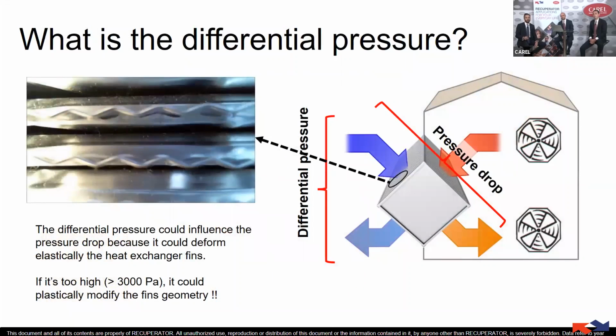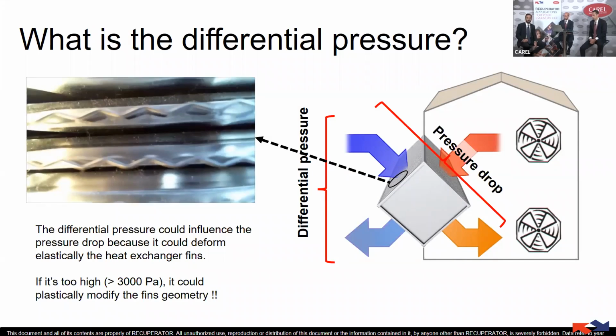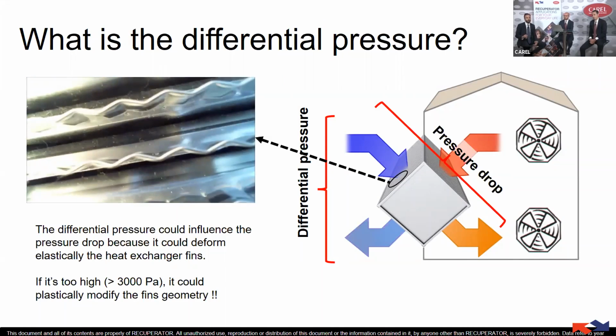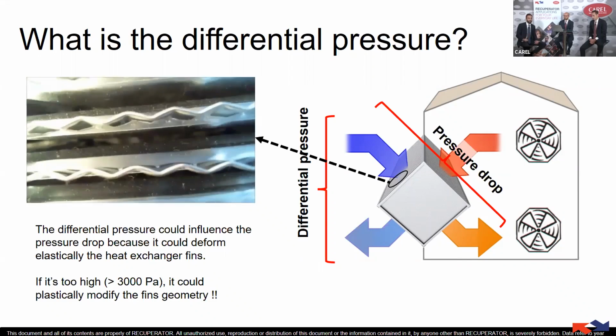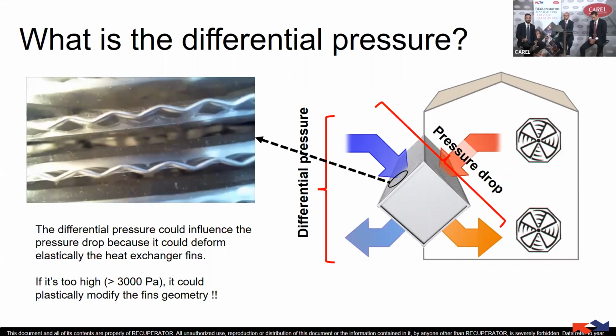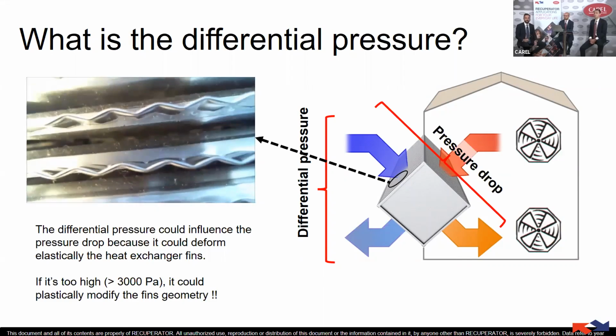Just a few words about the terminology, because it's important to understand the differential pressure to know how to manage the leakage. The differential pressure is different from the pressure drop. The pressure drop is the loss of energy of the airflow that passes through the heat exchanger, while the differential pressure is a difference in pressure between two different airflows. We also have a video, and this differential pressure mainly influences the pressure drop itself because it modifies the size of the gaps, as it is a force pushing on the plate.